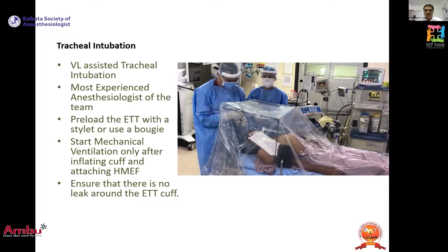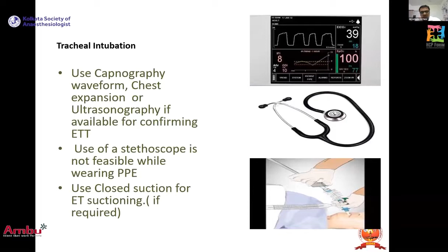After intubation, always attach a filter first, inflate the cuff, and then start ventilating the patient. Do not start ventilating a patient without inflation of the cuff or without the HME filter. Confirmation of the endotracheal tube should be done with capnography only, because auscultation is not possible with full PPE on. And when you want to suck out through the endotracheal tube, always use a closed suction unit.